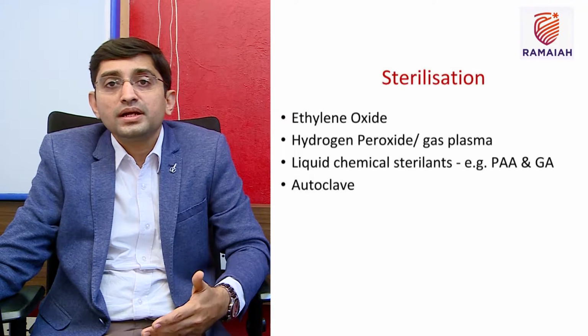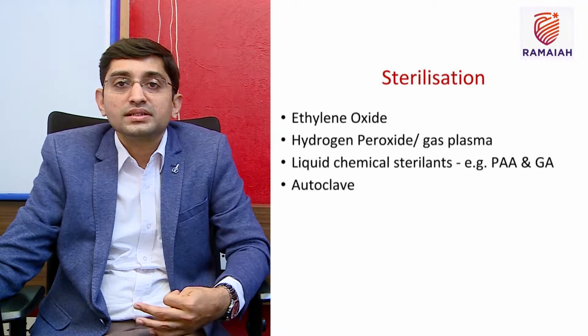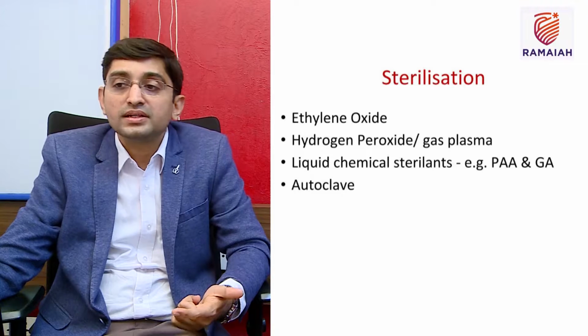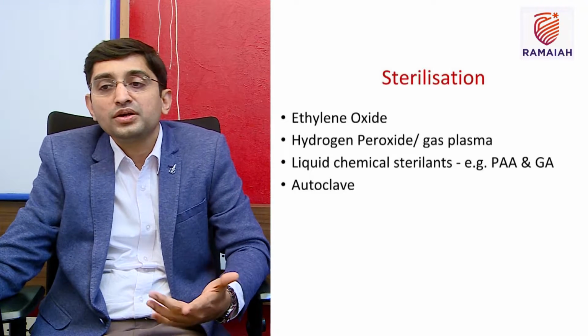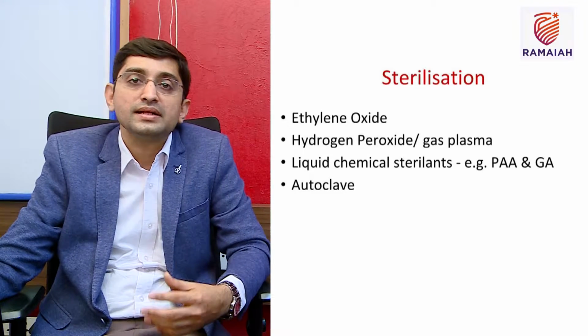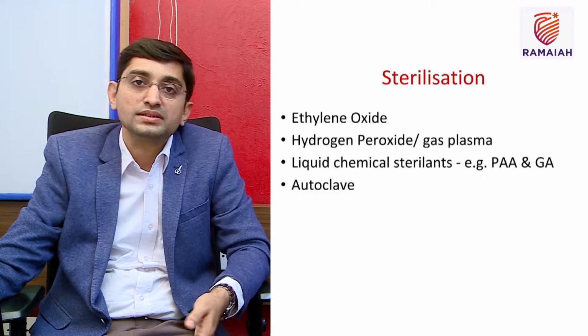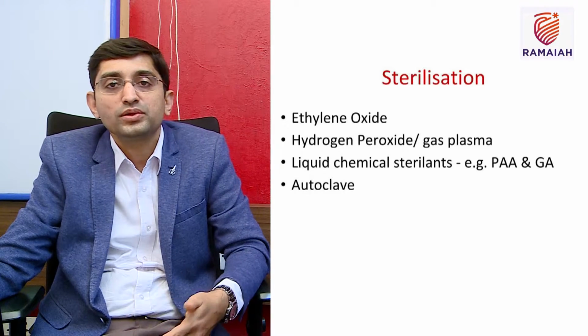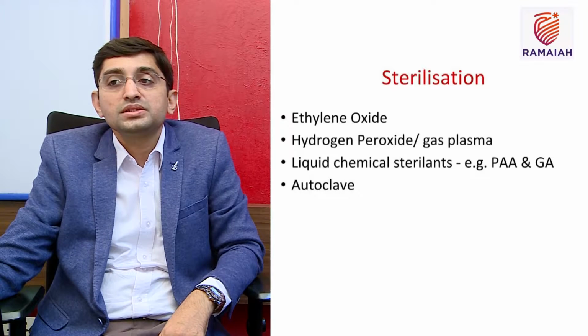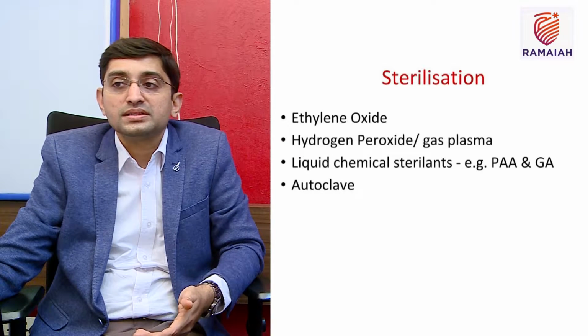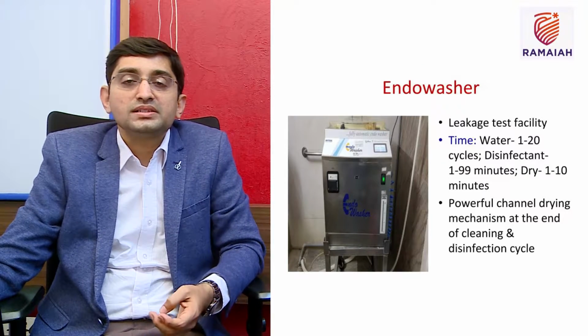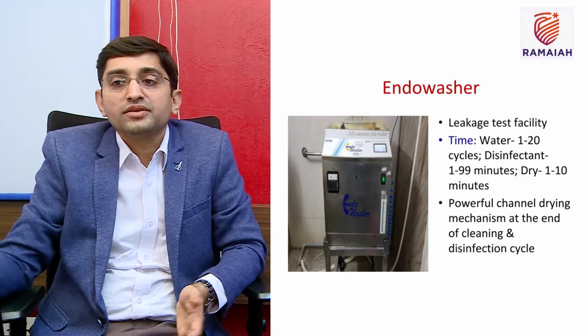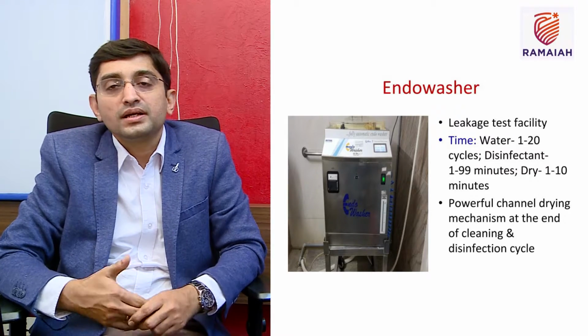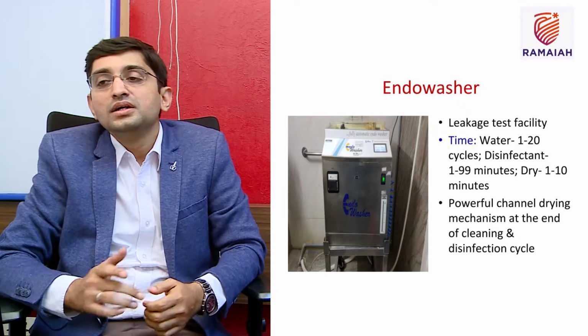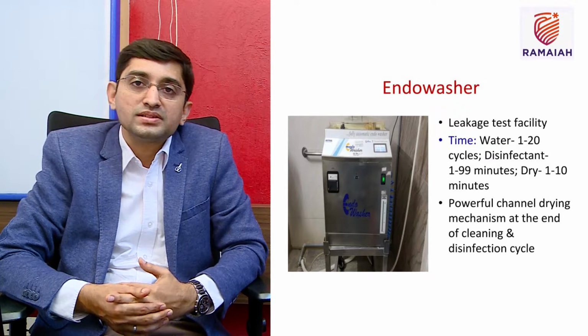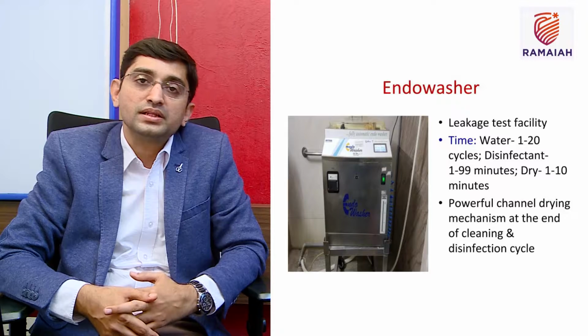Sterilization can be done by using multiple methods. One is ethylene oxide, second one is hydrogen peroxide. Liquid chemical sterilants can be used, PAA or glutaraldehyde, or autoclave. Predominantly the accessories are done by ethylene oxide as well as autoclaving. For endoscope reprocessing, we tend to use the multi-enzyme cleaner as well as the endo washer. The endo washer is basically a machine; different companies make them, like Olympus and Mitra, and there is a leakage test facility available within the endo washer.